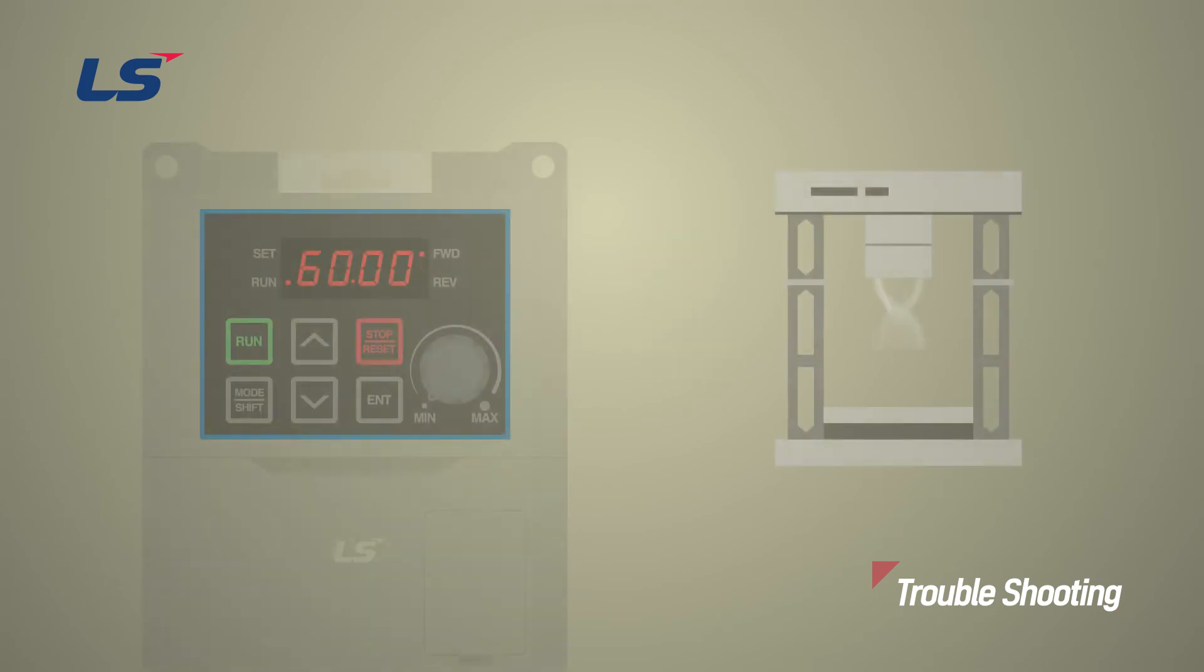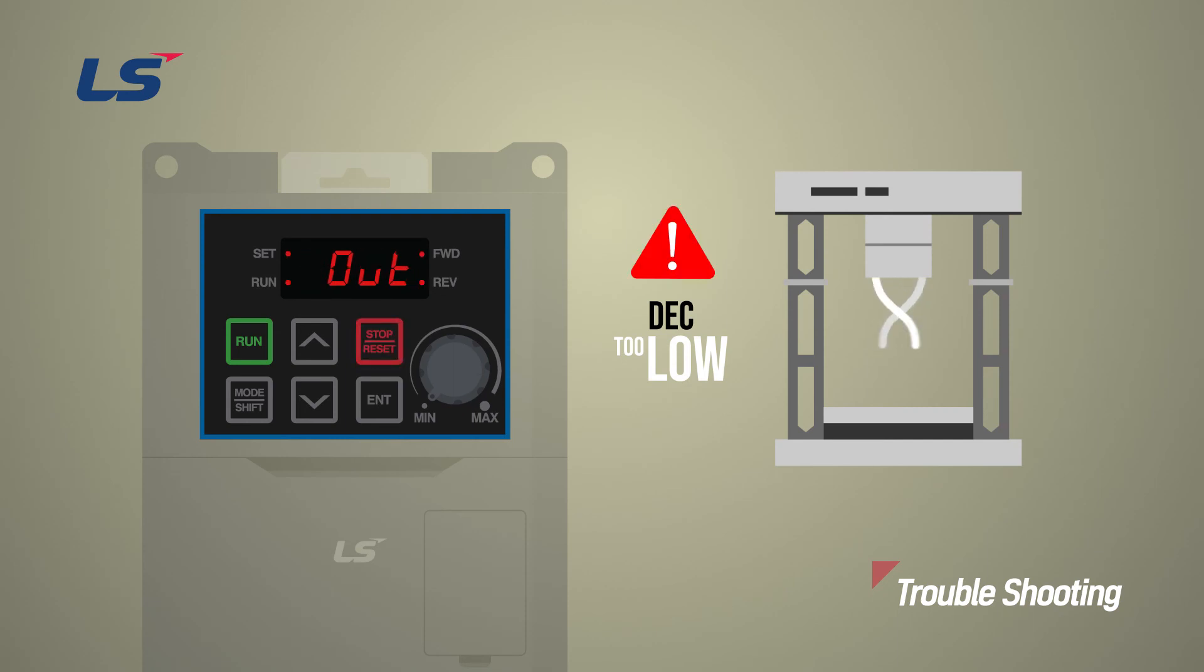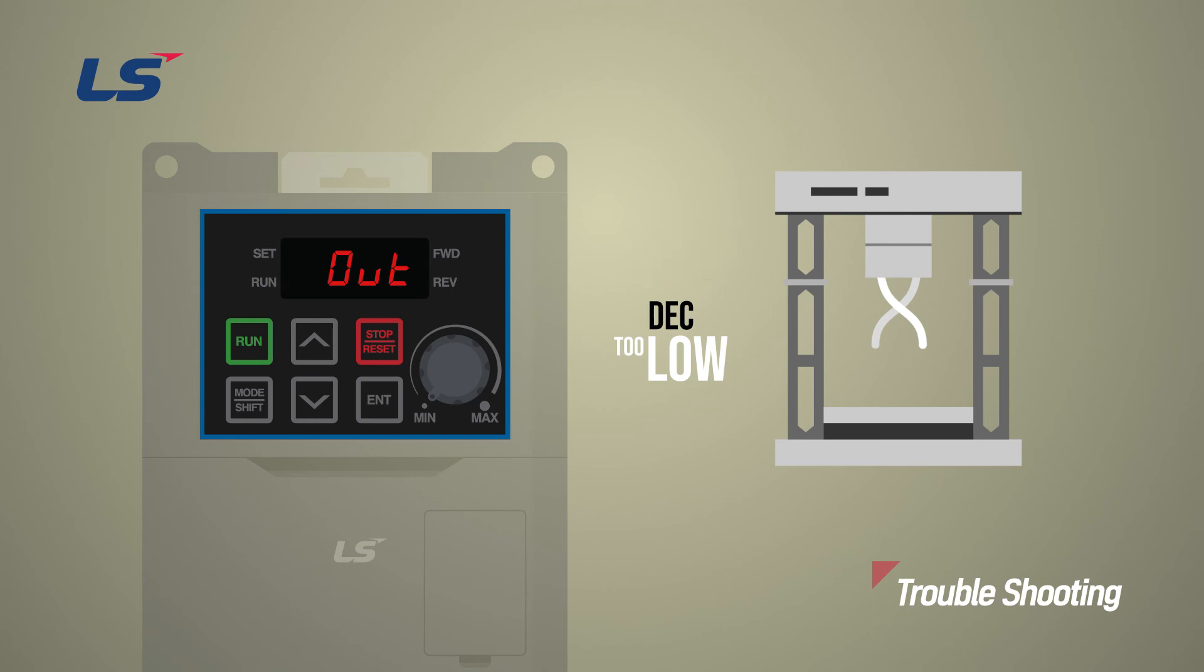If the deceleration time is too short, a large amount of regenerative energy is generated, and an overvoltage trip may occur. To prevent this from happening, the acceleration and deceleration time setting should be set to an appropriate value for the load.